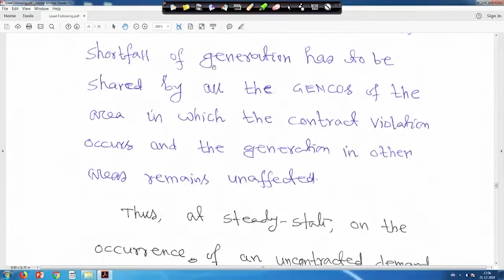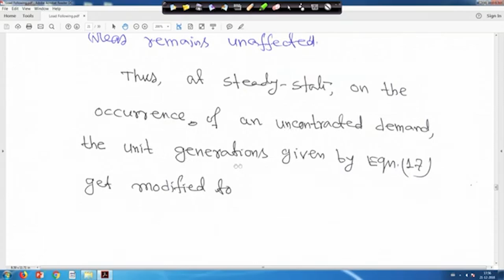So, this I skip, I have already shown that for that case too. So, now that means at steady state, on the occurrence of an uncontracted demand, the unit generation given by equation 17 gets modified too. So, we write like this, that delta Pg1 steady state, delta Pg2 steady state, delta Pg3 steady state, delta Pg4 steady state is equal to APF, that is ACE participation factor, into delta PL1 dash UC, that is the uncontracted power demand, if any, demanded by Disco 1, distribution company 1. Delta PL2 dash UC means uncontracted power demand demanded by Disco 2, right. Then this is delta PL3 dash UC, that is uncontracted power demand demanded by Disco 3, and delta PL4 dash UC, that is uncontracted power demand demanded by Disco 4, right.